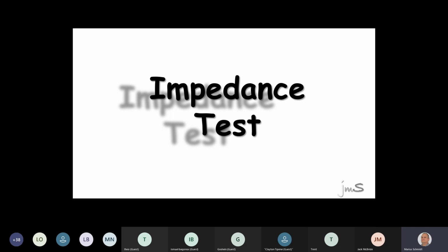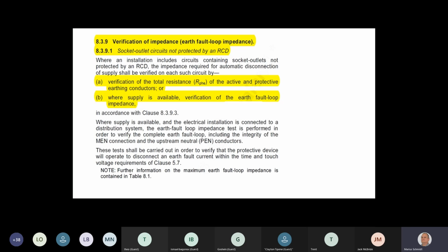I'm going to answer all your questions for you. Live? Can I do it dead? Yes or no? No, you can't. Tonight I'm going to show you can. Right, firstly, what does 3839 state? 8.3.9 states you do a fault loop impedance test only on sockets, not on RCD. You don't have to do it on lights, you don't do it on the stove, you don't do it on the hot water cylinder. You only do it on a plug which is not an RCD.